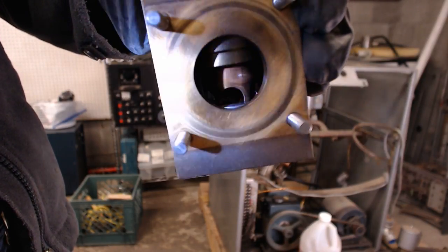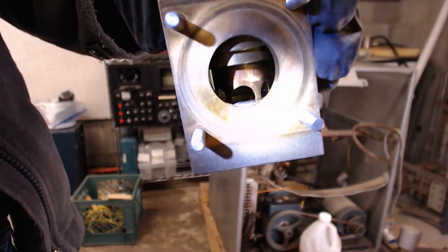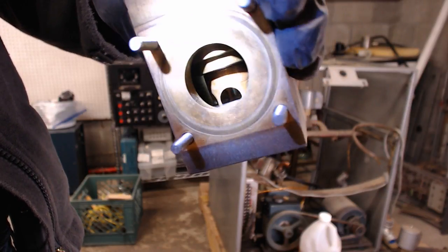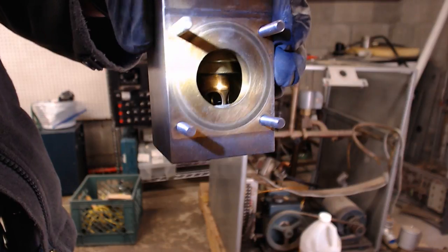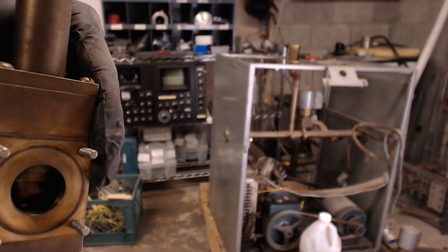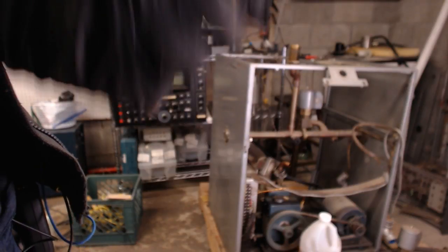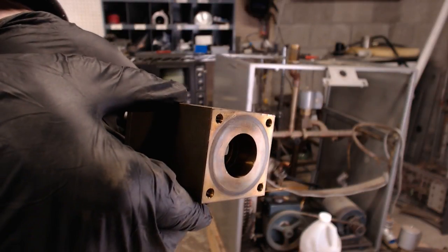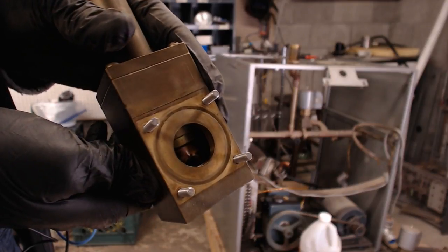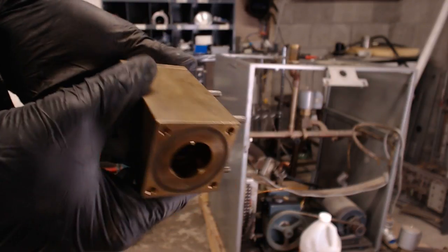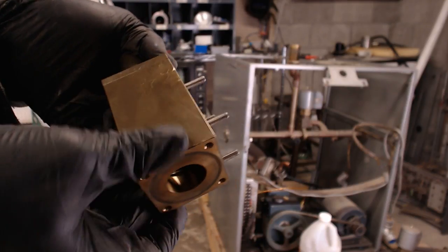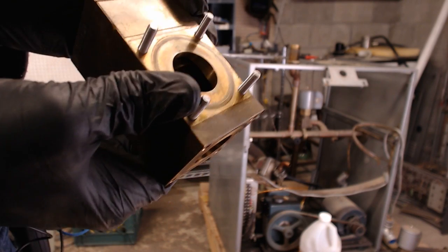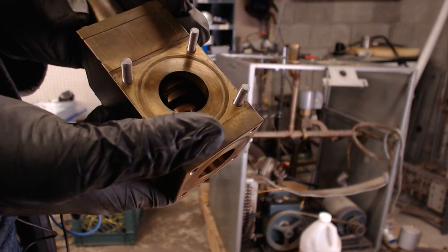So you'll see the plunger goes all the way through that hole and has some holes in the copper that is the plunger. And that just gives you a little bit more control over the throttling nature of this. And so you can see it's got these two flat faces, and those two flat faces are what makes the vacuum seal. So an O-ring gets pushed up against that. And that's for the big two throttling valves on this thing. That's how those work. And the other two are gate valves, and I'll show one of those off in a bit once I get it pulled out.